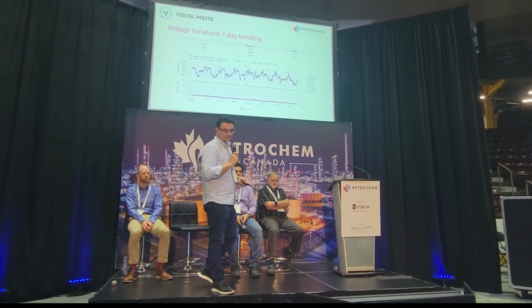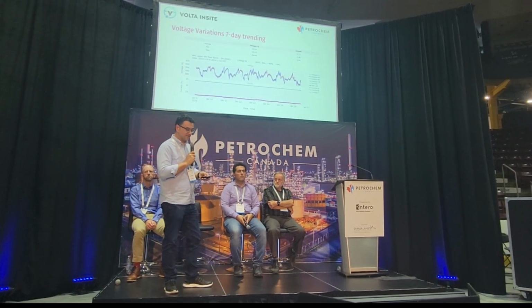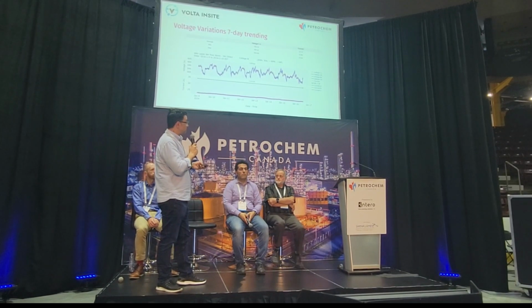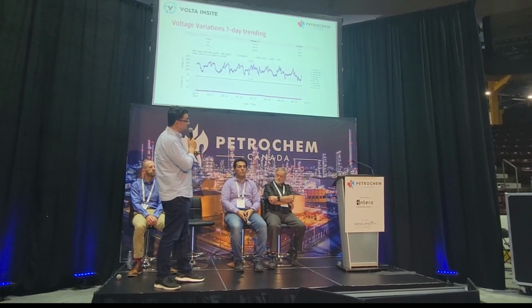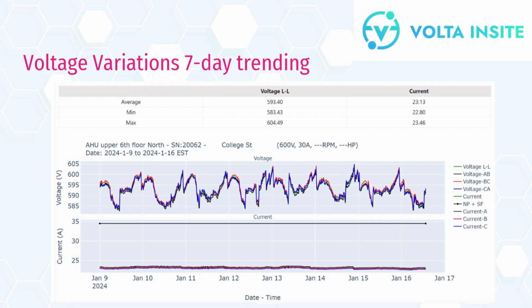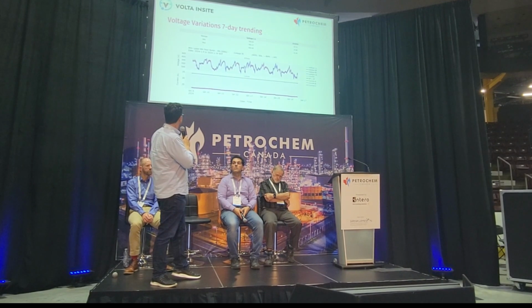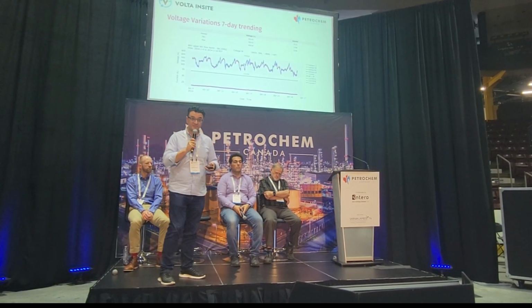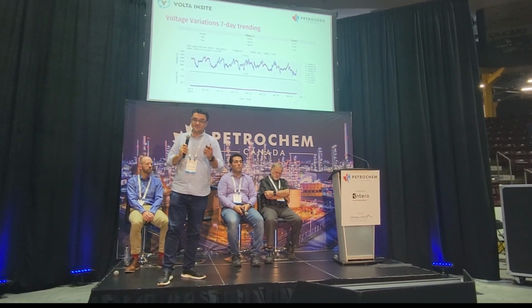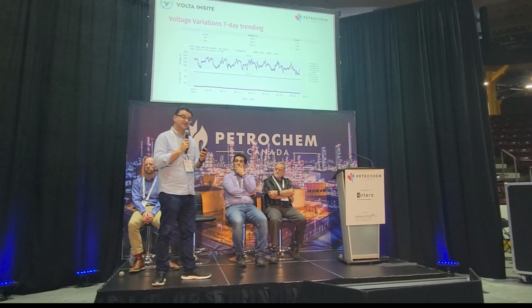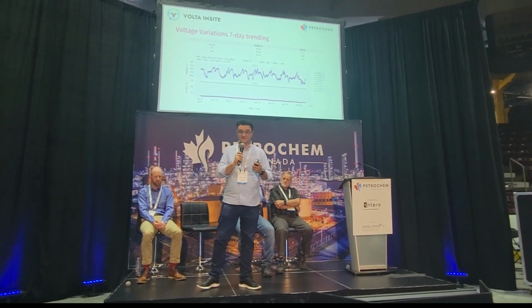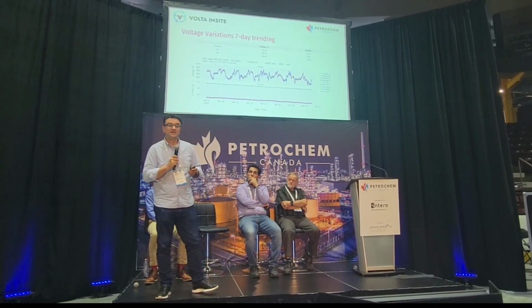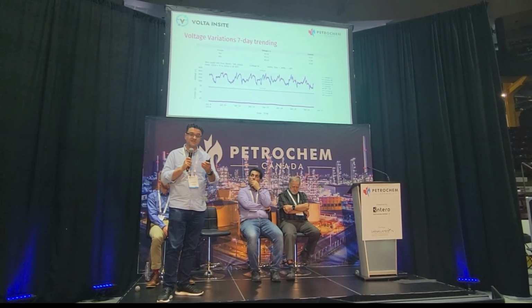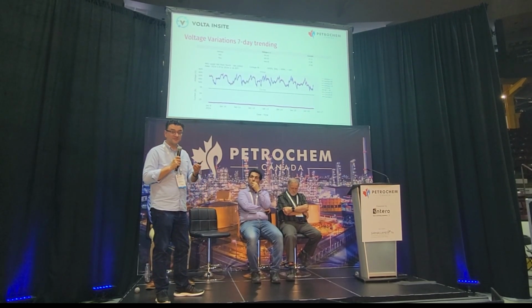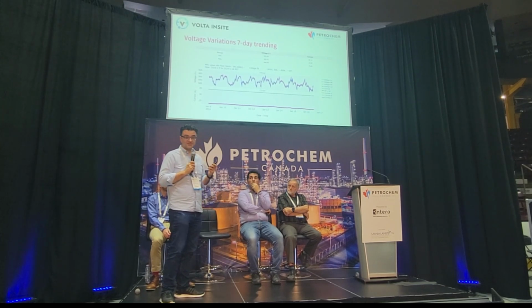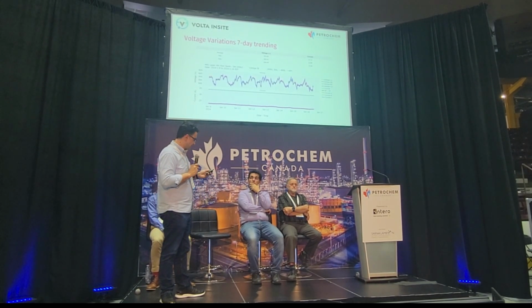Here's another example of voltage variations that happen from the utility side specifically, and it has to do with the utility trying to keep up with demand. This is an example of downtown Toronto. You'll notice that the voltage is around 600 volts during the start of the day, and towards the end of the day, you're dropping below 585. This is important, especially in Canada, because we think that a 600 volt system is sufficient to buy equipment at 575 volts. So if the utility is allowed to vary the voltage plus or minus 10%, on the positive side, you will end up burning motors. So understanding what the utility level is, what the utility is actually giving you is important.